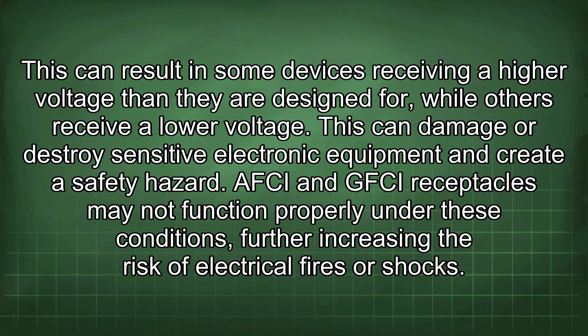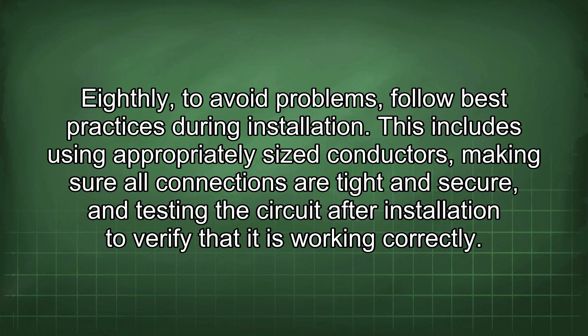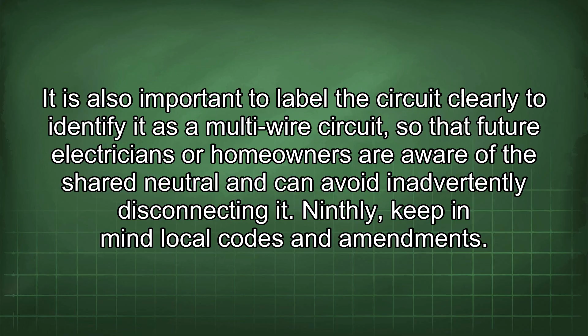Eighthly, to avoid problems, follow best practices during installation. This includes using appropriately sized conductors, making sure all connections are tight and secure, and testing the circuit after installation to verify that it is working correctly. It is also important to label the circuit clearly to identify it as a multi-wire circuit, so that future electricians or homeowners are aware of the shared neutral and can avoid inadvertently disconnecting it.